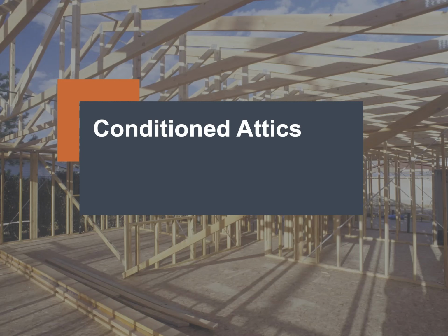A conditioned attic involves moving the thermal boundary to the roof plane. It creates a large area of conditioned space above the typical ceiling. This also means that you have to heat and cool more building volume, which will increase the energy use slightly. However, savings from the increased HVAC efficiency should far outweigh the small amount of additional heat loss you get from that larger surface area and volume.